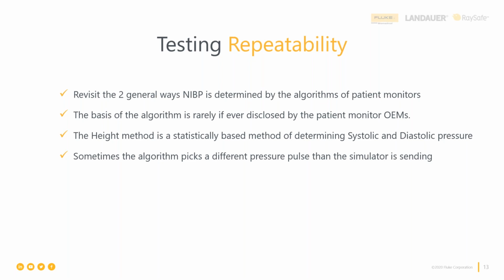So it's not about accuracy at all. In no way is dynamic simulation about accuracy. It is about, if I send a signal or cause a pressurization to happen, let's say 120/80, that no matter what I see on the measurement system display, the NIBP display, as long as every time I send 120/80, it is the same, then it is repeatable. Has nothing to do with accuracy. Get accuracy out of your brain when it comes to this. It is about repeatability and stability. That's all it's about. And I need to do both ways of assessment in my workflow.